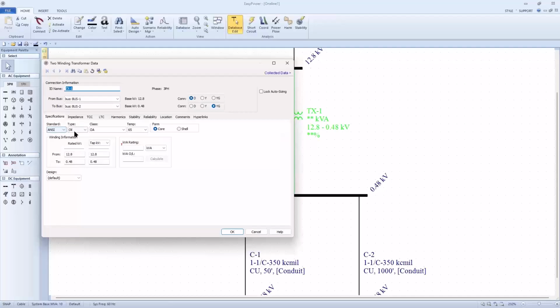It's an ANSI standard oil filled. So I pick out oil filled class OA, which means it didn't have forced air. The temperature rating was a fixed 65-degree rise. The connections was a delta with a Y grounded, the delta Y grounded. The rating has a little red dot by it, which means it's mandatory data. The kVA rating on his nameplate was 1,000 kVA.